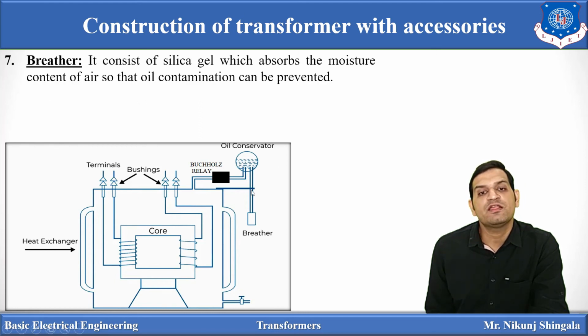Next one is the breather. Here you can see one breather is connected with the oil conservator tank by pipe. We know the function of the oil conservator tank is to take the expansion and contraction of the oil. Now, what is the function of the breather? It consists of silica gel which absorbs the moisture content of the air so that oil contamination can be prevented in the oil conservator tank.